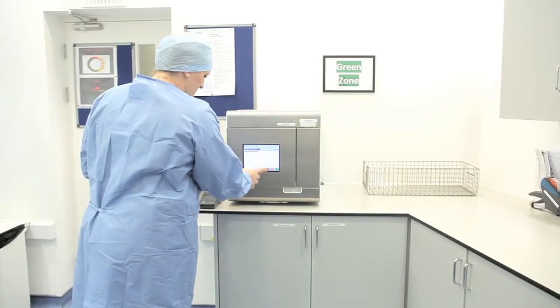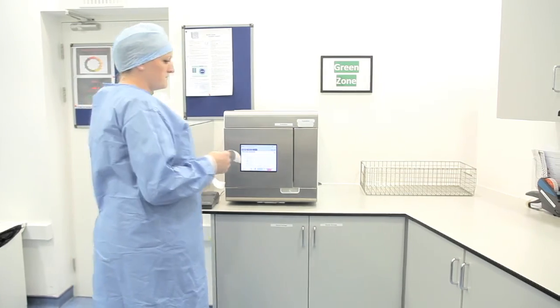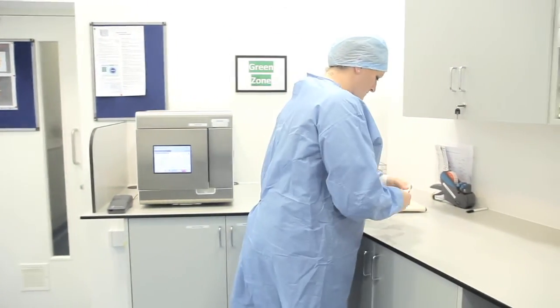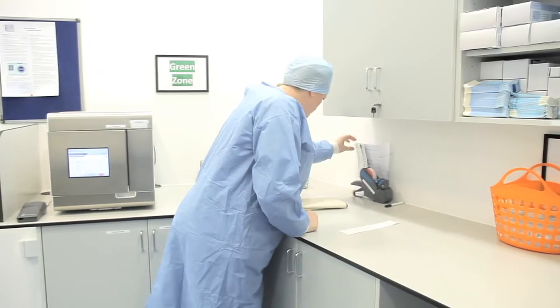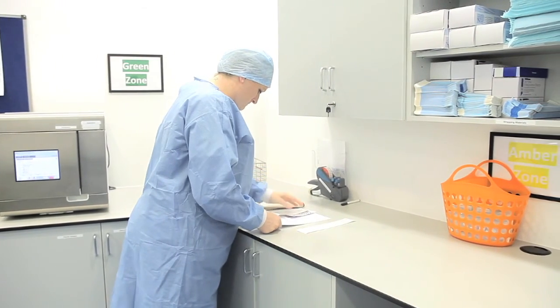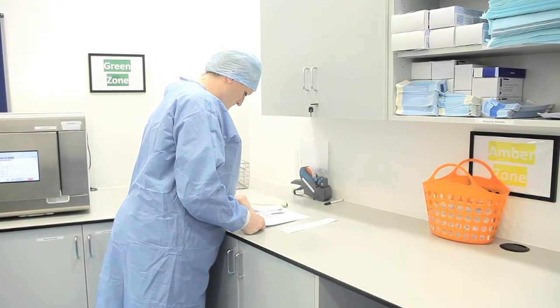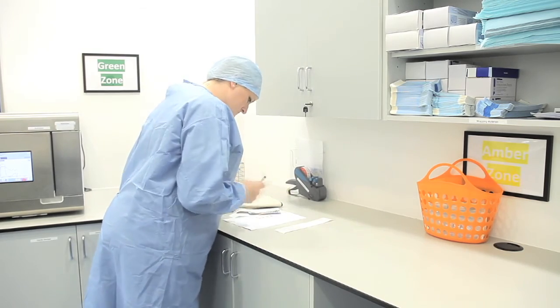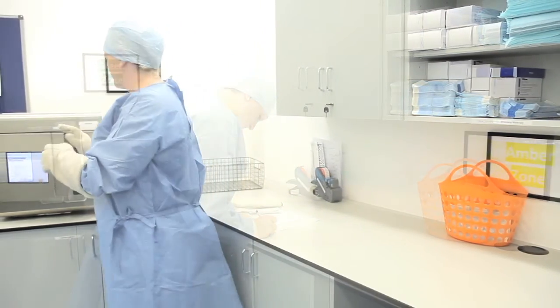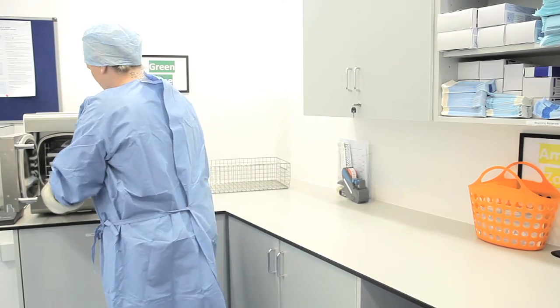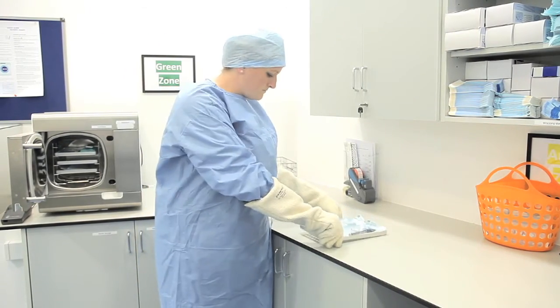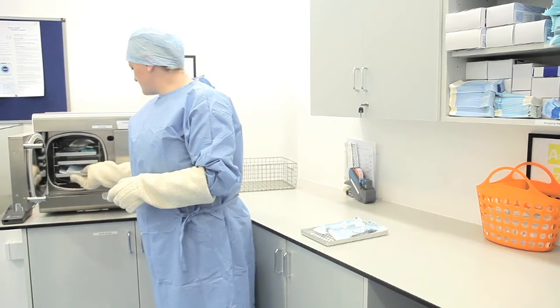Any cycle not meeting the criteria, although indicated as a pass by the automatic controller, should be rejected. The load should be repacked and sterilised, and the steriliser removed from service until the cause of the fault has been established and remedied. A failure of the cycle recording device should also be a cause to reject the sterilisation cycle.